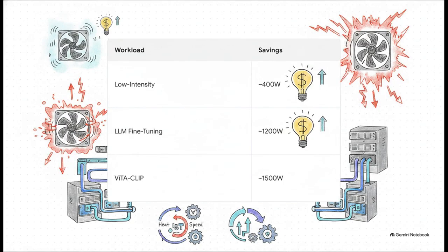And when you map this against how intense the workload is, the savings scale dramatically. For low-intensity tasks, where the air cooling fans don't need to run at full blast, we save about 400 watts. But during high-intensity LLM fine-tuning, those savings jump to 1,200 watts. And at peak intensity, for vision language models like ViTA-CLIP, we are saving an incredible 1,500 watts per single node.